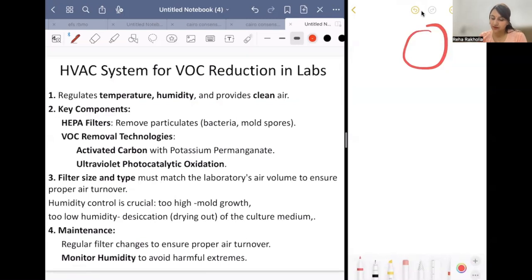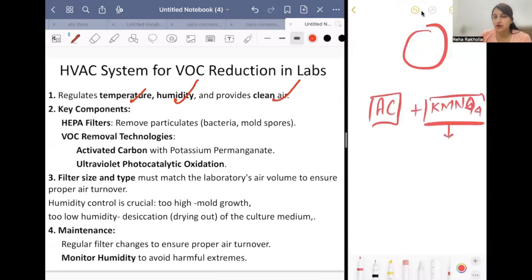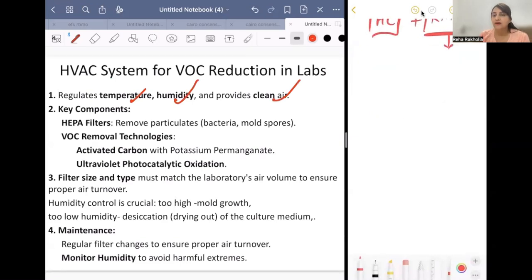Now, HVAC system for VOC reduction. The HVAC system regulates temperature and humidity and provides clean air. A key component is the HEPA filter, which removes molds and spores, while VOC removal is done by activated carbon. Activated carbon is used along with potassium permanganate, which is an oxidizing agent that oxidizes VOCs into non-toxic substances.